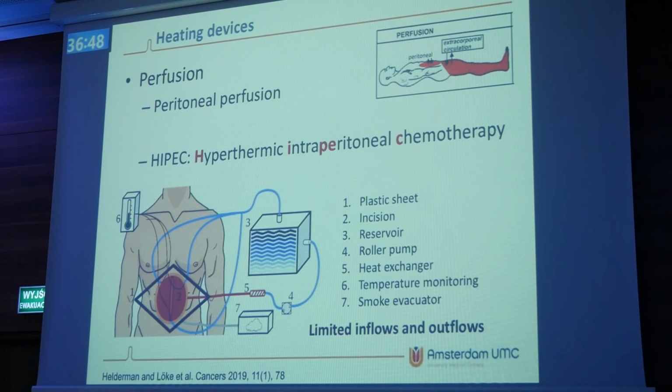So these are then all the ingredients needed, where part of the concerns are that you try, on the one hand, to have a simple form of circulation, but you also want to prevent chemotherapy from evaporating into the operating theater. You want to have a homogeneous temperature distribution in your target region, and you want to monitor that.